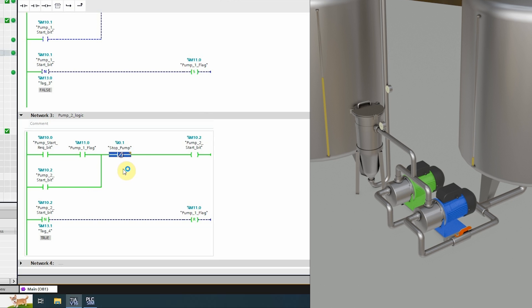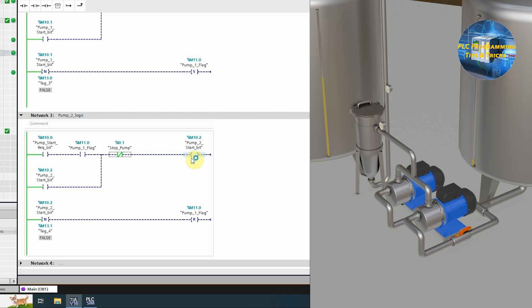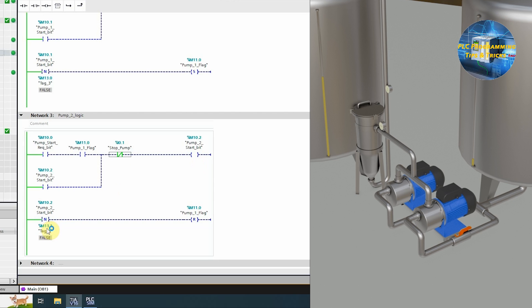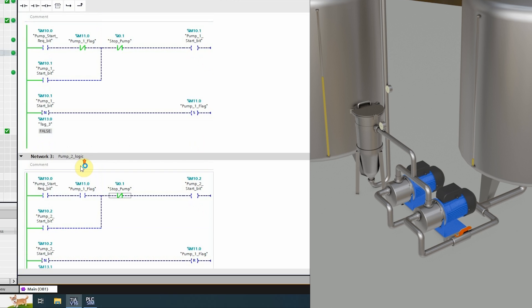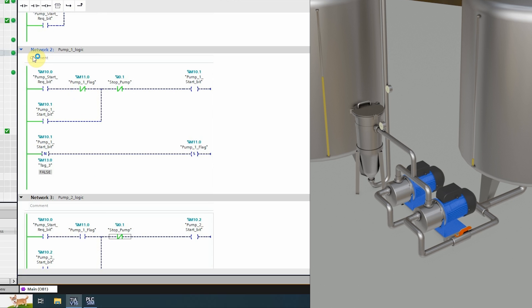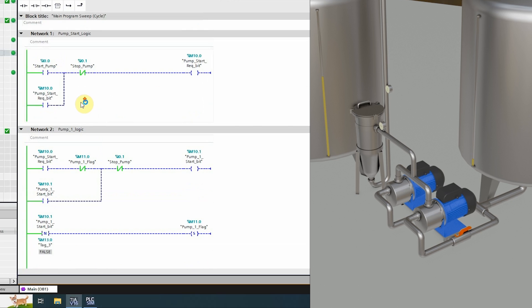Now we press the pump stop button I0.1. It will turn off the pump 2 start bit M10.2, and on the negative edge it will reset the pump 1 flag bit M11.0. It has opened up this contact, and now it will prevent pump 2 from starting on the next pump start request. Now coming to network 2, this contact M11.0 is now closed and will allow pump 1 to start on the next pump start request.